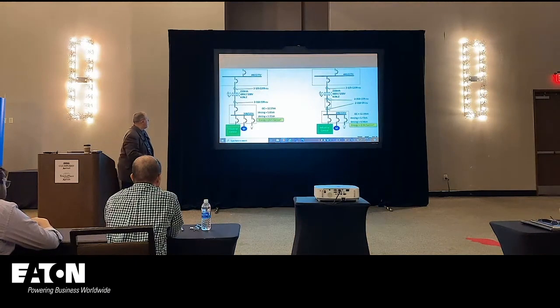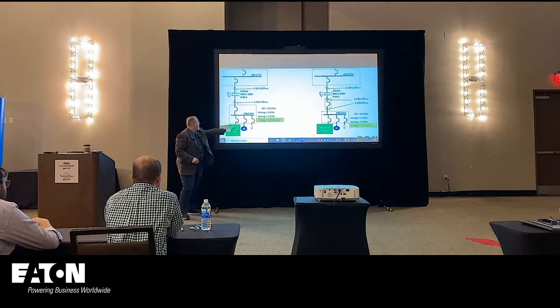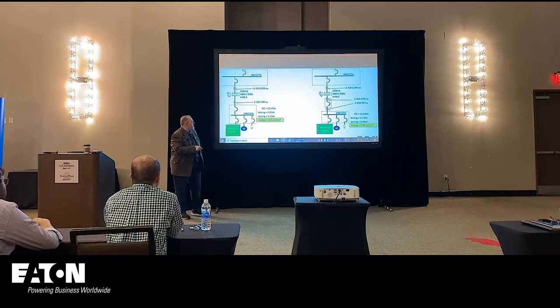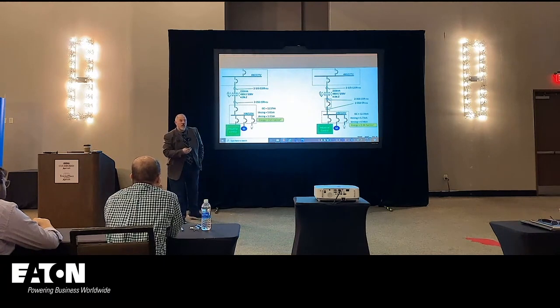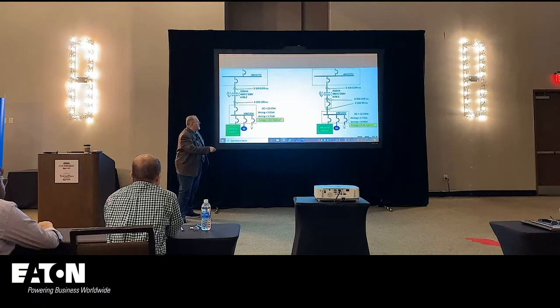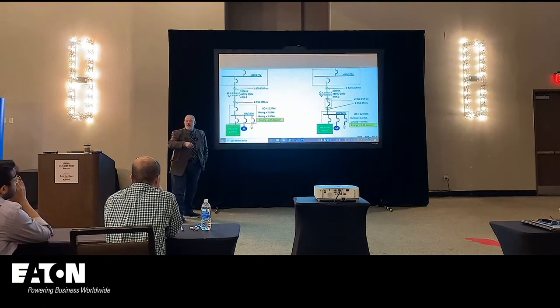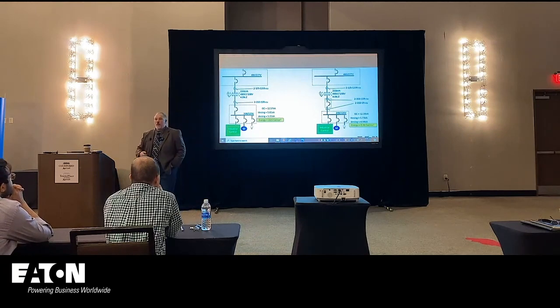And this is why. Look at this. 23.5 calories on the secondary of this transformer. Why? Because it's relying on that device for the clearing time. But if I simply move the overcurrent device out, and maybe I integrate it with the transformer itself, now my incident energy, where the likelihood that I'm going to do justified energized work, has gone from 23.5 to 0.34. I'd rather work on 0.34. Actually, I'd rather be on the couch.